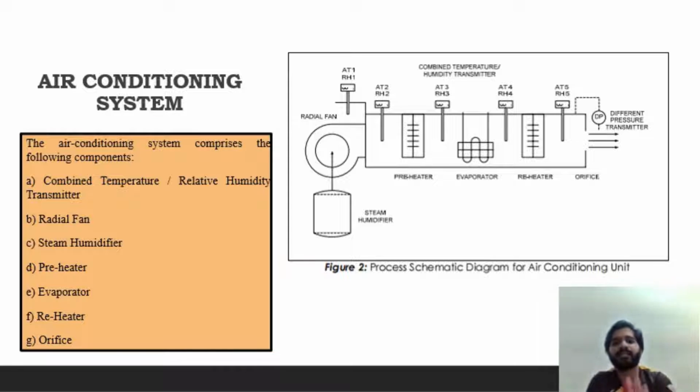The next part is the steam humidifier, which has an electric power consumption of 2 kilowatts. The next part is the preheater, which consists of 4 electric air heaters with an output of 0.5 kilowatts each. The individual heaters can be configured to enable heating powers of 0.1 to 2 kilowatts to be set.